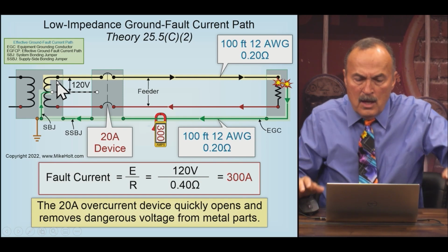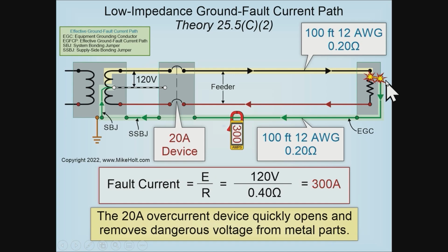It's a word, a name only. I mean, it means something. See this green path right here? From here all the way back here, the National Electrical Code calls it an effective ground-fault current path, just to give it a name. But it represents components. Don't have to worry about this. We're going to be covering this when we get into bonding and grounding. That's a supply side bonding jumper, system bonding jumper, equipment grounding conductor. When you bring all those components together, it gives you an effective ground-fault current path for the purposes of facilitating the opening of the protective device. So Mario, what rule talks about facilitating the opening of the overcurrent device? That would be 250.4(A)(5). It was A5. It was A5.